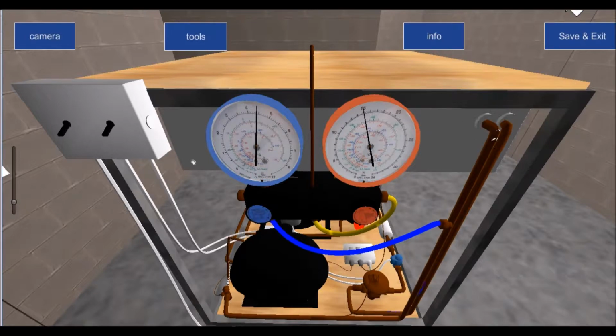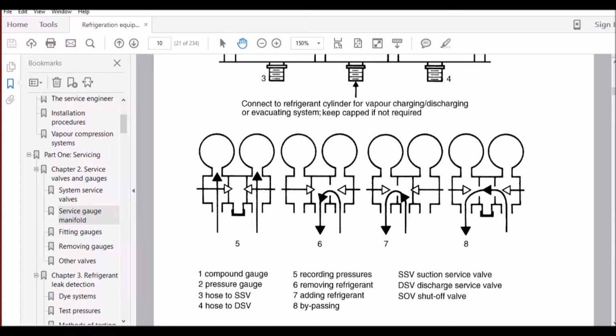Now, if this shut-off valve was open, and this shut-off valve was open, then we would be going back to the scenario that you see in the book, this scenario here. The 15 bar would be coming across into the 4.5 bar. So basically what you would find is there'd be a slight drop on the 15 bar on your gauge manifold and a slight increase on your 4.5 bar, and you would be getting constant high pressure going across into the low pressure, and that would give you the same characteristics as a compressor not pumping properly. So that would give you the same sets of faults, or the same relationship, as a compressor not pumping. So it's very important that we isolate. By keeping the manifold valves closed, we are isolating the high side from the low side.